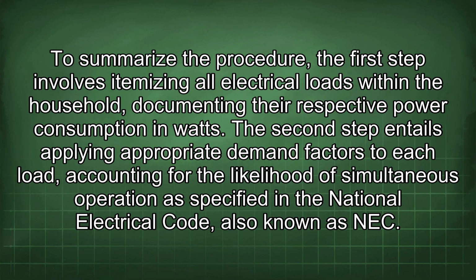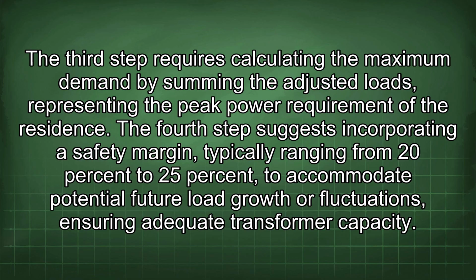To summarize the procedure, the first step involves itemizing all electrical loads within the household, documenting their respective power consumption in watts. The second step entails applying appropriate demand factors to each load, accounting for the likelihood of simultaneous operation as specified in the National Electrical Code, also known as NEC. The third step requires calculating the maximum demand by summing the adjusted loads representing the peak power requirement of the residence. The fourth step suggests incorporating a safety margin, typically ranging from 20% to 25%, to accommodate potential future load growth or fluctuations, ensuring adequate transformer capacity.